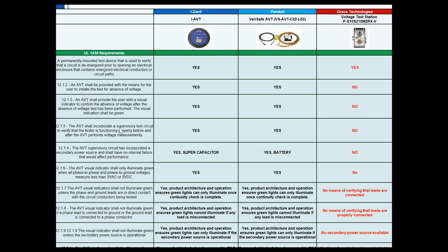12.1.5, the absence of voltage tester shall incorporate a supervisory circuit. Again, i-Gard i-AVT, yes. VeriSafe, yes. Grace, no. The absence of voltage tester supervisory circuit has incorporated a secondary power source. We use a supercapacitor, Panduit uses a battery. Grace does not comply. The absence of voltage visual indicator shall only illuminate green when all three phases, phase to phase and phase to ground, are less than 3 volts AC or 3 volts DC. The i-Gard i-AVT complies. VeriSafe by Panduit complies. The Grace product does not comply.